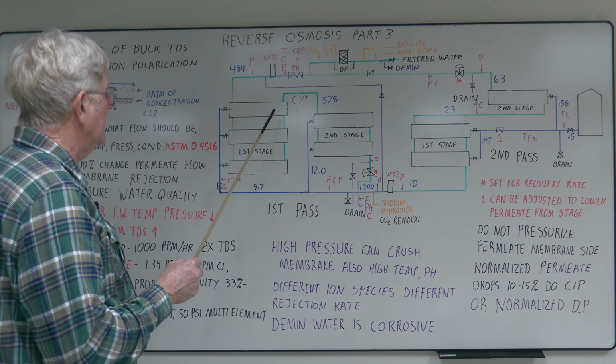These are taken out as a percent of the conductivity. There's a little bit of slip, solute slip or salt slip. So this should be a little bit higher because you're dealing with a little bit higher conductivity water. This can be a big problem in the summertime if your water changes. If you go to well water from surface water and you get a lot higher numbers, it's going to change all this quite a bit. And you could get into a scaling potential.